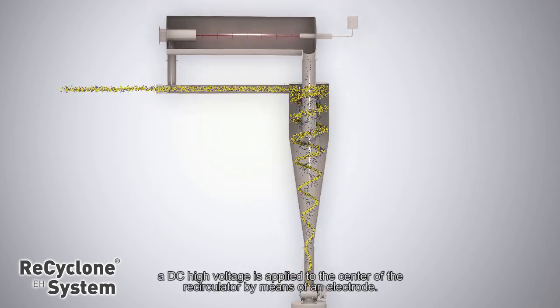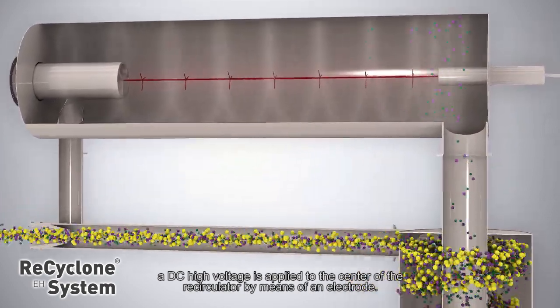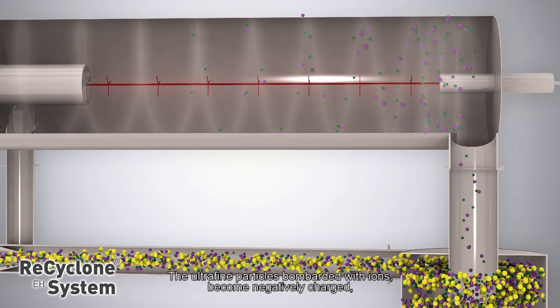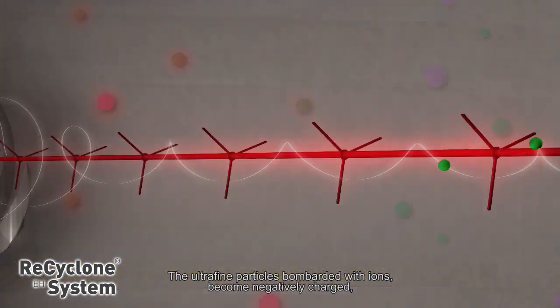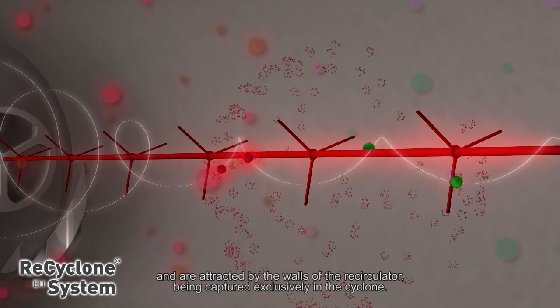A DC high voltage is applied to the centre of the recirculator by means of an electrode. The ultrafine particles bombarded with ions become negatively charged and are attracted by the walls of the recirculator, being captured exclusively in the cyclone.